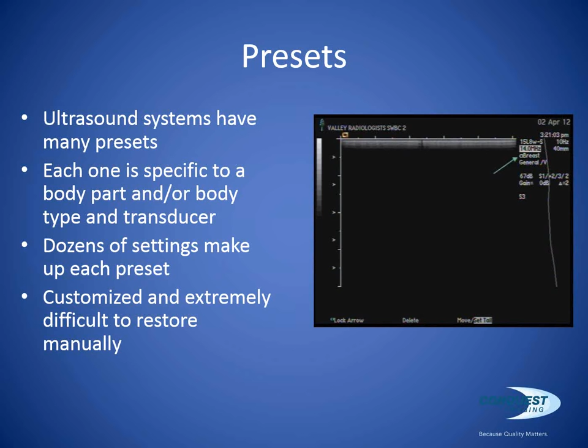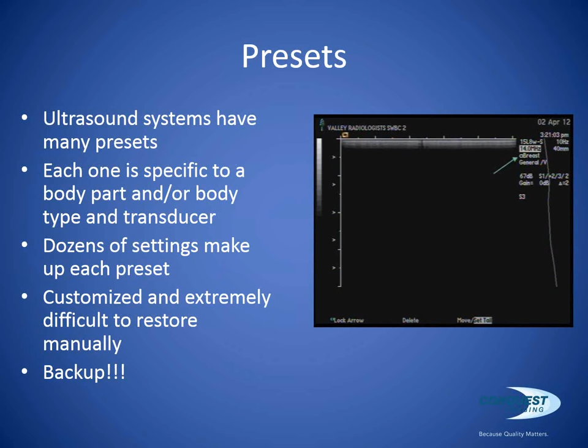If any of you are technician readers, which I'm hoping most of you are, I've written multitudes of articles in there, and about half of them talk about making system backups. It is critical that all these settings that are in these machines are backed up. To restore them manually requires going on site and sitting down with a sonographer and going through all the different types of exams and manually tuning the machine. Each sonographer is different. Each system's a little bit different, and factory presets are never good, and so each system does have custom presets. So you want to make sure that you back up and back up again. Again, if any of you read any of my articles, you'll see that I'm a huge proponent of backing up. Every system I've ever worked on has multitudes of backups, and that is to ensure that these presets are saved, and it also mitigates downtime.